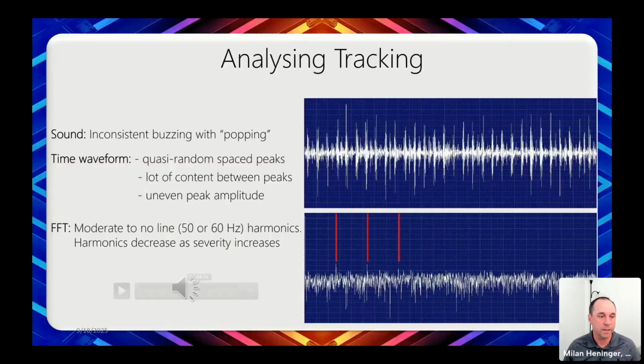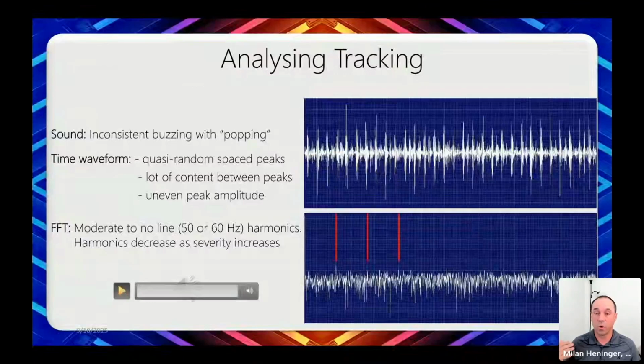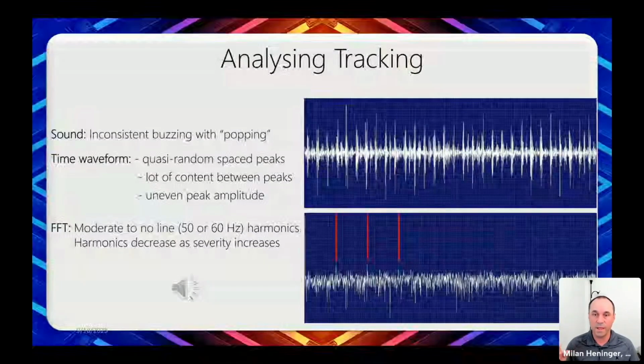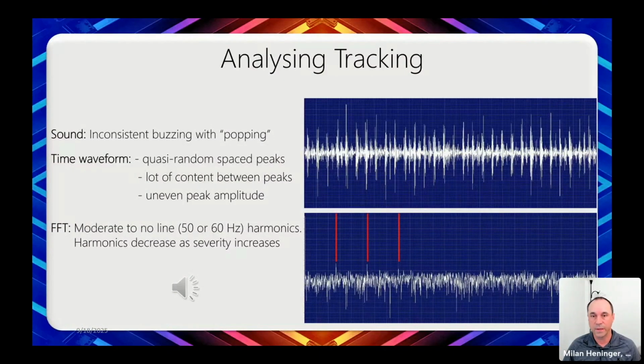So here's an example of what tracking sounds like. You get a little bit more popping. It's a little more aggressive. You hear more of that inter-peak content that comes in. It just gets noisier. And that's one of those characteristics. When you've done enough of this, you can listen and go, that sounds like corona. And you can listen and go, yeah, that definitely sounds like tracking. But we still are going to go back. We're going to use the software. We're going to do time analysis. We're going to do some spectral analysis to confirm those diagnostic steps.